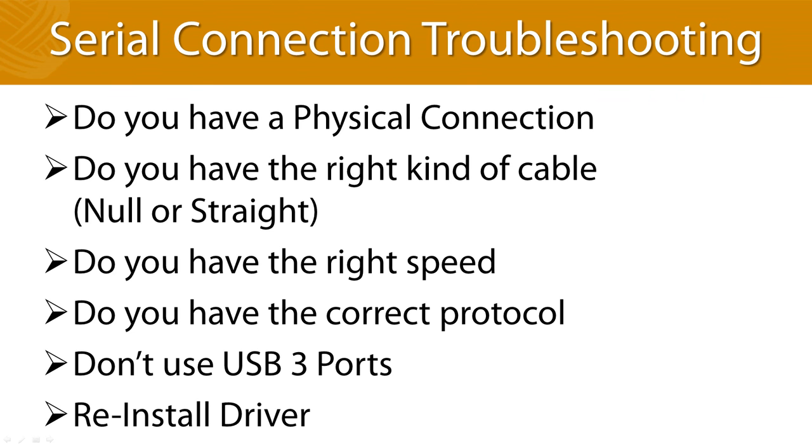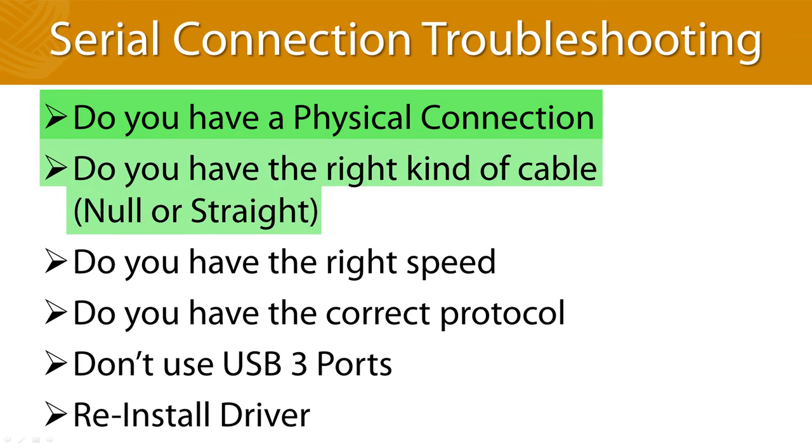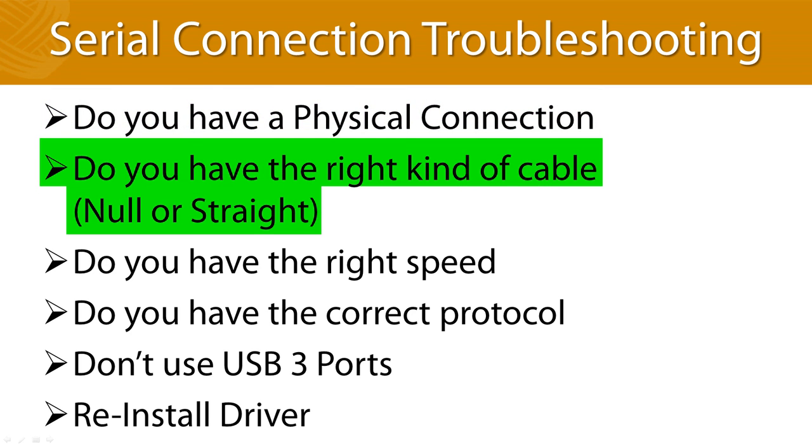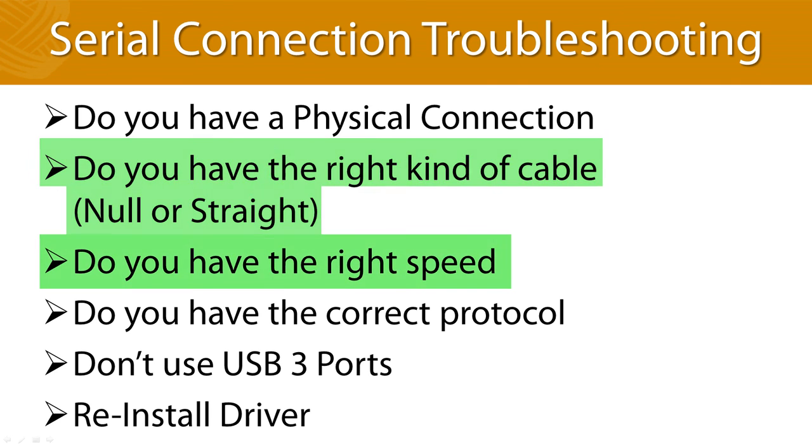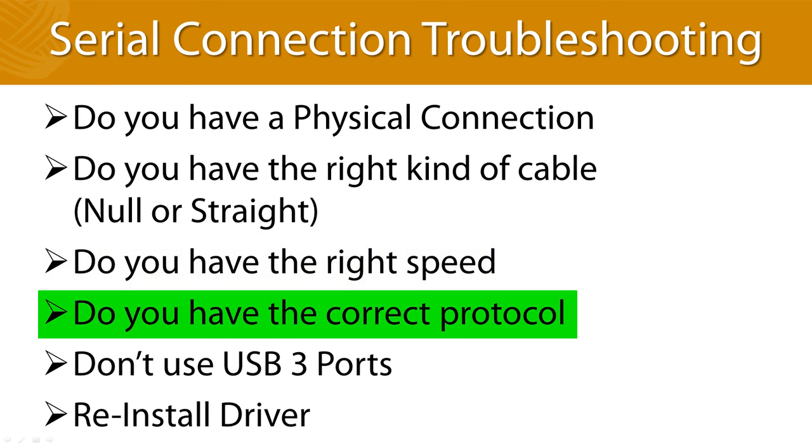What happens if you can't communicate? Start at the beginning and make sure you followed all of the steps. Step number one, do you have a physical connection? Do you have the right kind of cable? Try adding a null modem to make sure. Is the baud rate correct? Is the relay communication port programmed with the correct protocol in the relay?